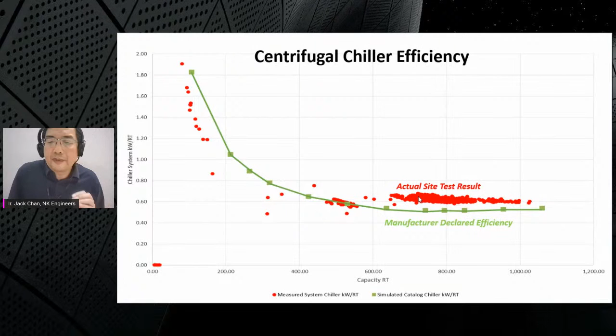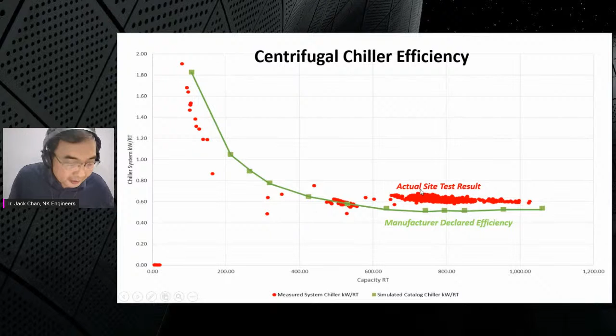You will find from this curve that it will never actually match, because sometimes the running conditions are different from the tested conditions. The test condition may be slightly different from the operating condition, especially your condenser entering temperature. Your cooling tower temperature may be higher than the one used for testing in the factory. But anyway, this is actually quite good, because it mirrors, and the difference is not very large.